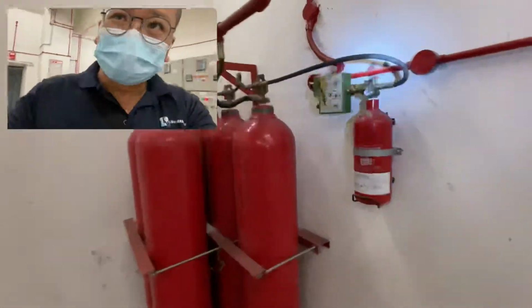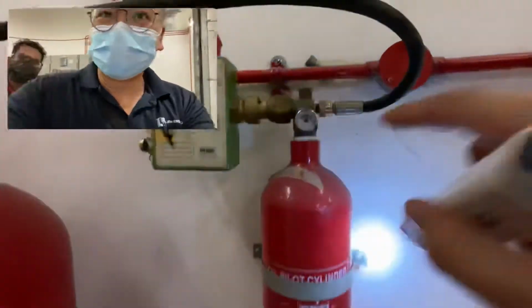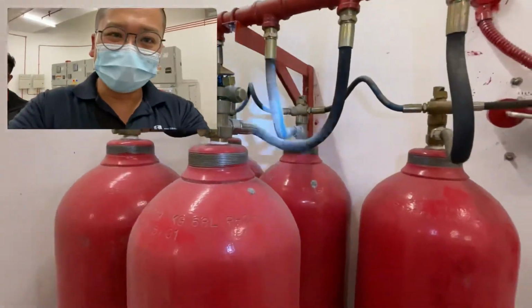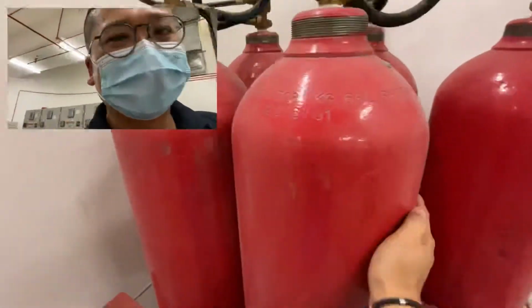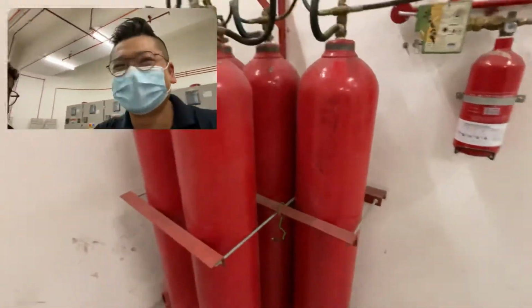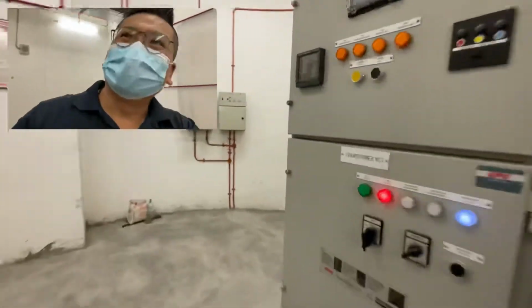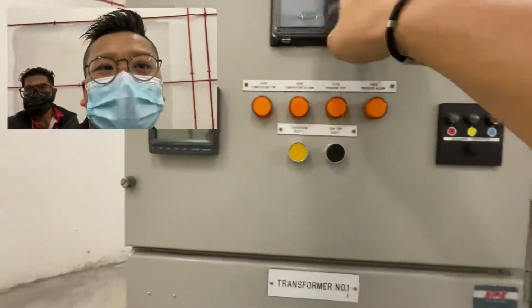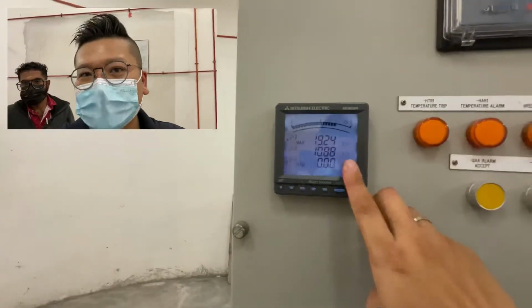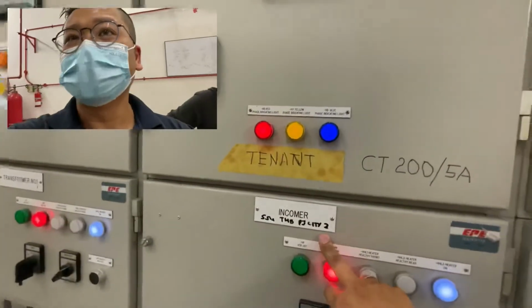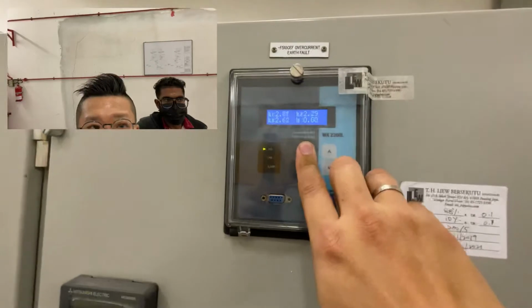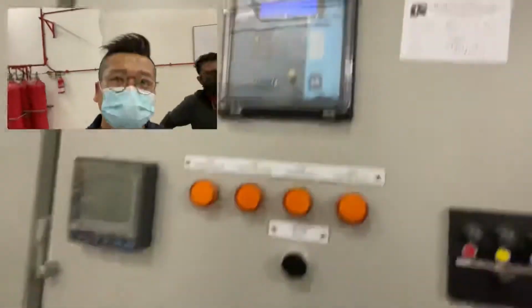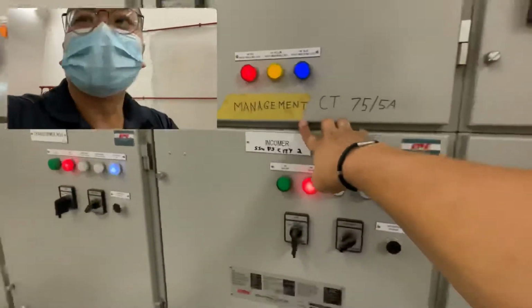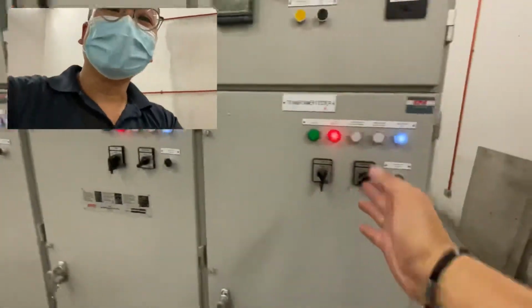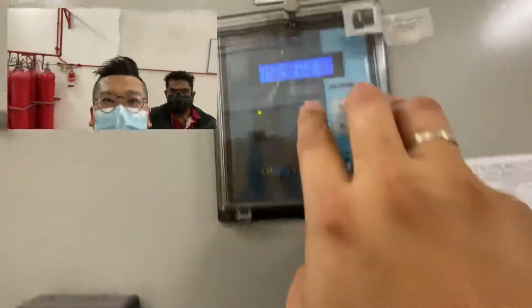Okay, let us see the CO2 panel and then the CO2 system. Pressure is okay. It doesn't discharge and it's not empty. There's an echo sound there, so it's not empty. Okay, let us check transformer number 1. No load currently. This is the voltage rating. Okay, this is incomer number 2. Around 2 amp, 3 amp. Load quite low. Transformer number 2, amp also quite low. This is the management side, 2 switchgear. One is incomer and another one is feeder to the transformer. 1 amp only, quite low.